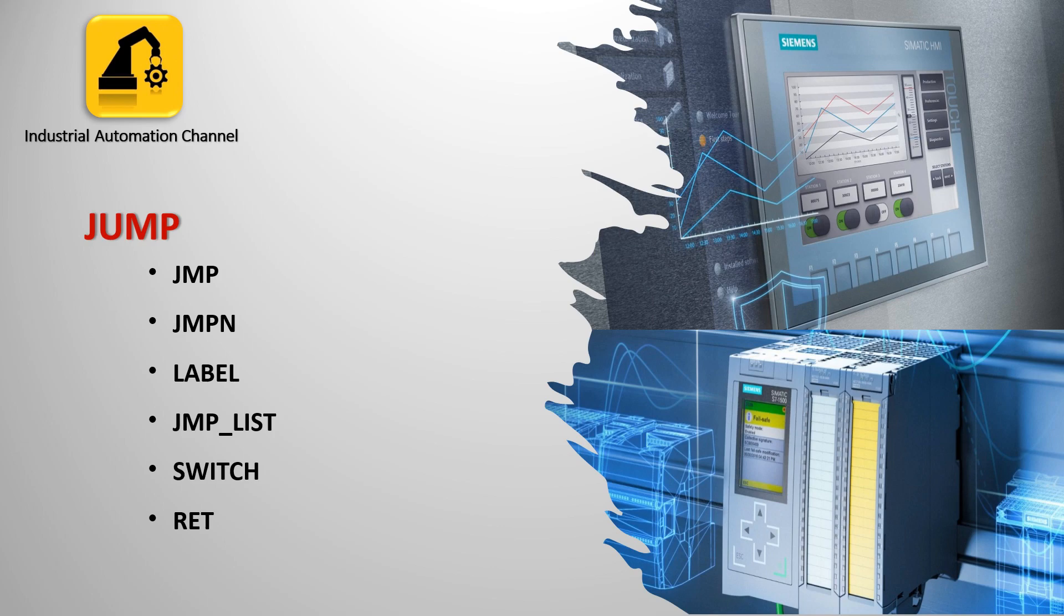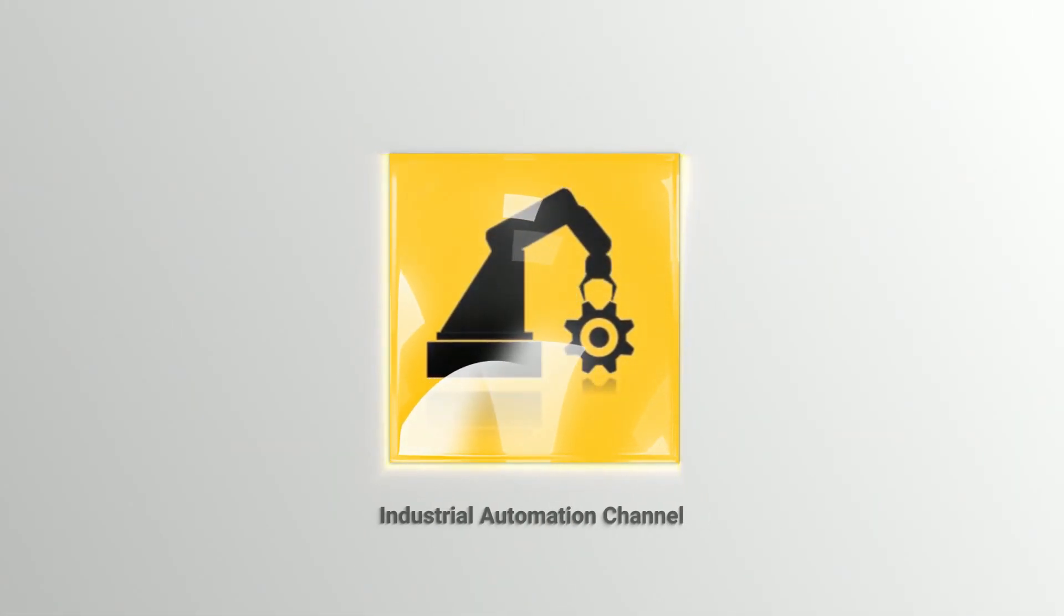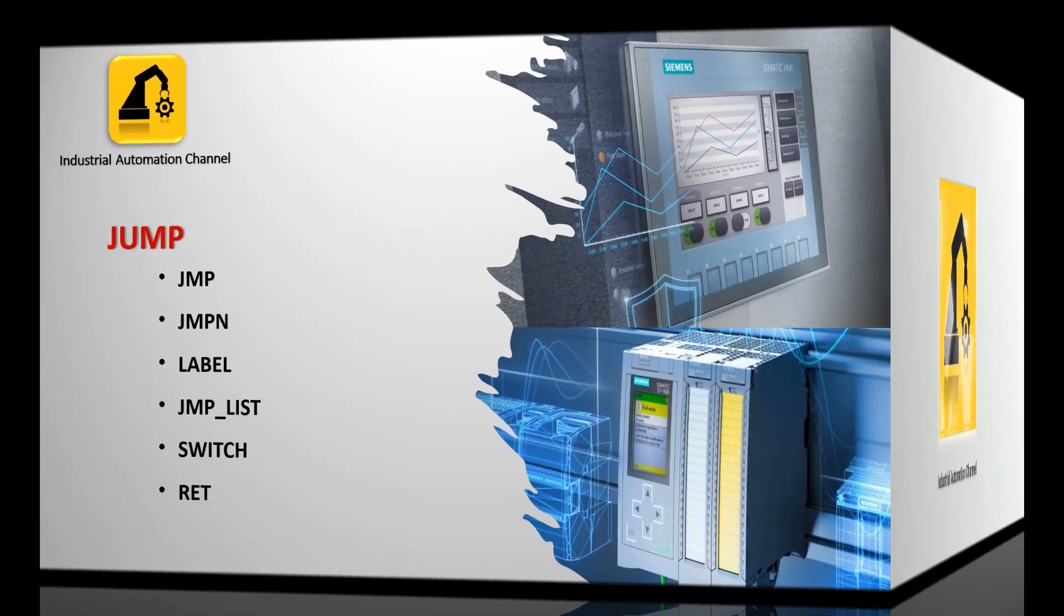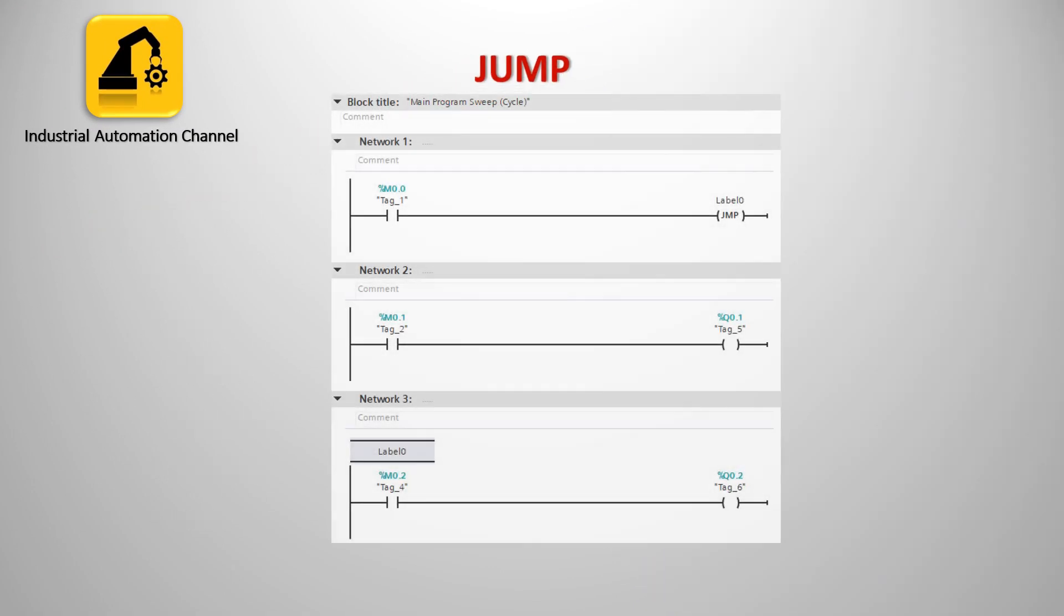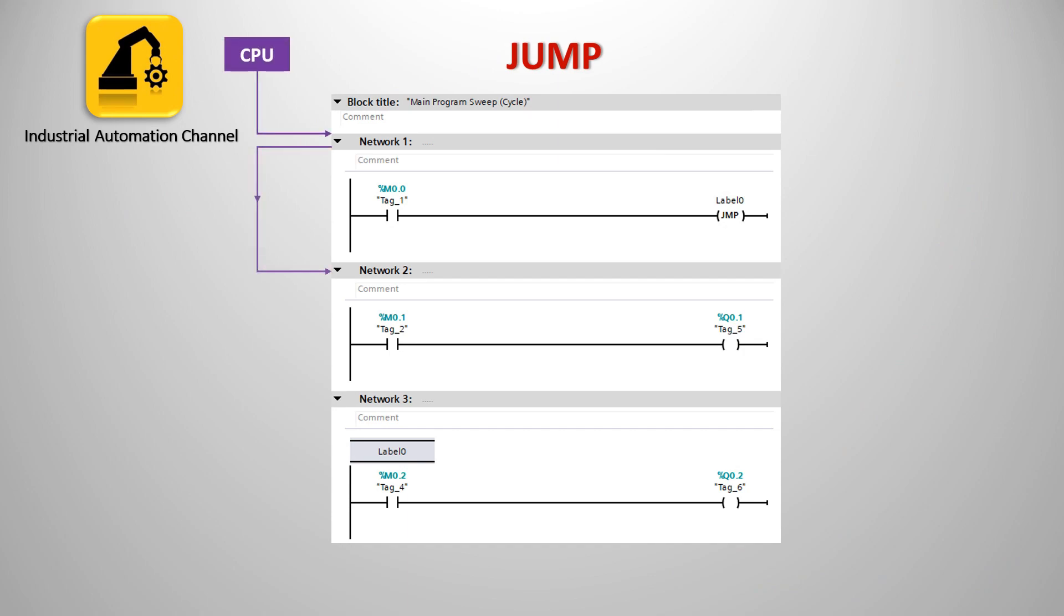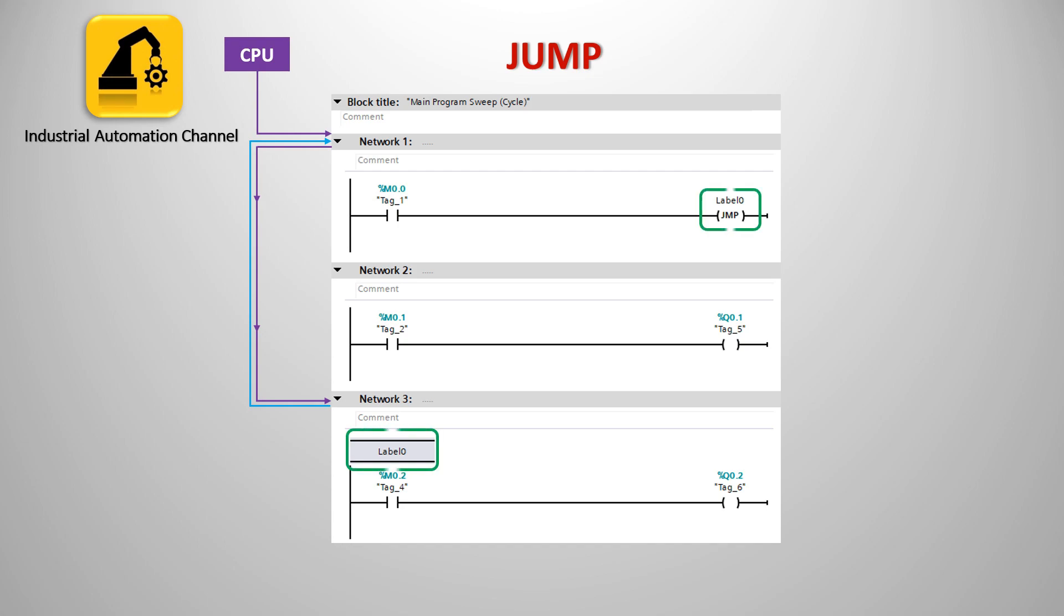Let's see how we can use these operations in TIA Portal. As you know when a CPU is executing any program in an OB, it will move from the top first network to the last network to scan the program from network one to the last one. This will be repeated over and over again. Sometimes we need to skip some networks and not let the CPU scan what we have written in a specific network. In this case we can use jump instruction.